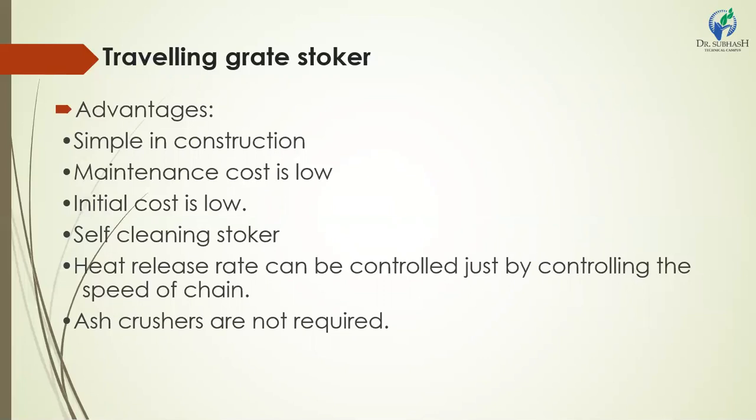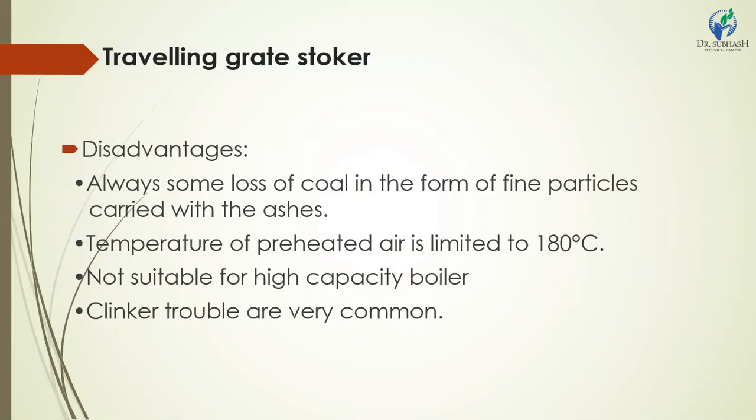There are some disadvantages also for grate stokers. The amount of coal the grate can carry is less, hence it cannot be used for high capacity boilers. We cannot use it for boilers of 200 tons per hour or more. Second, some amount of coal is lost, carried away in the form of fine particles with the gases.